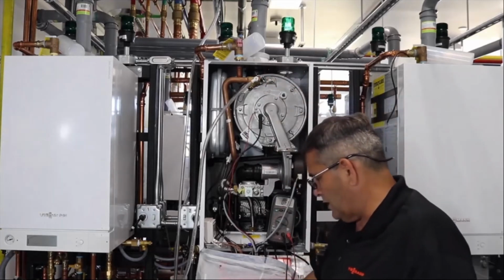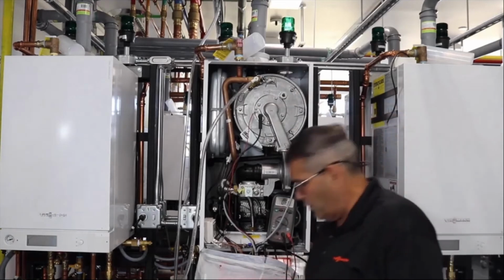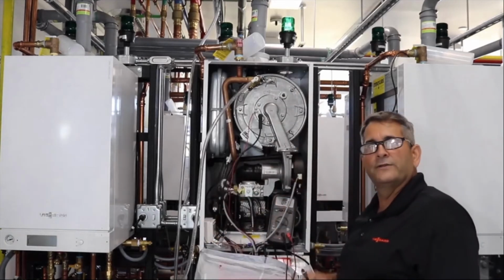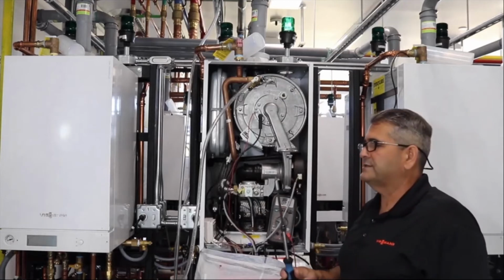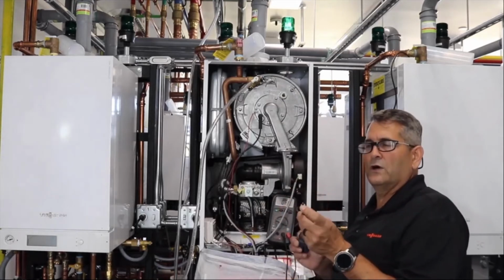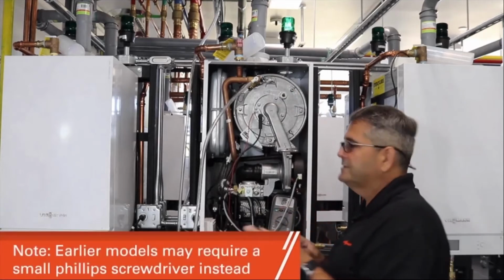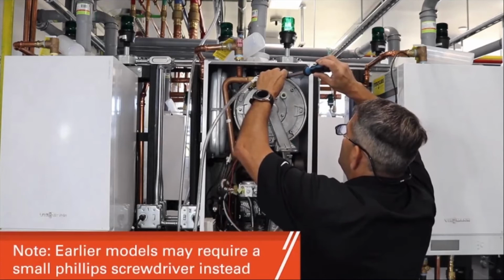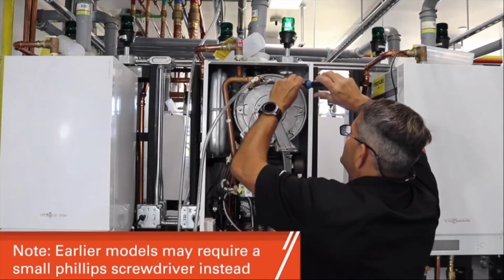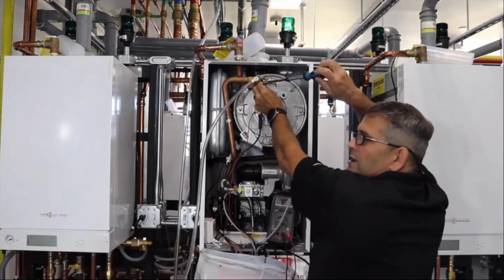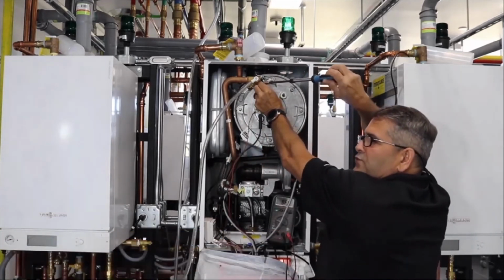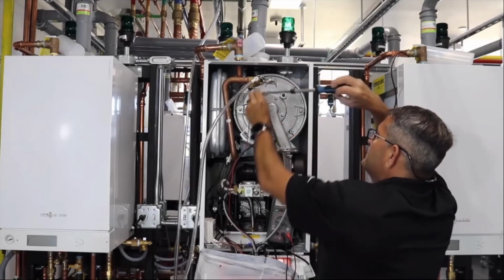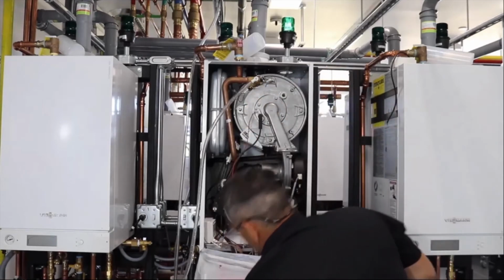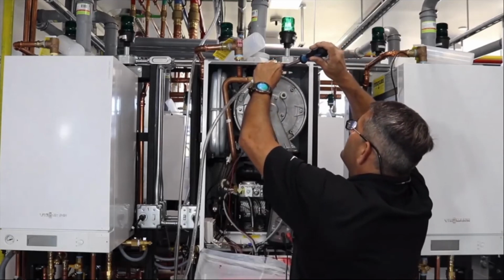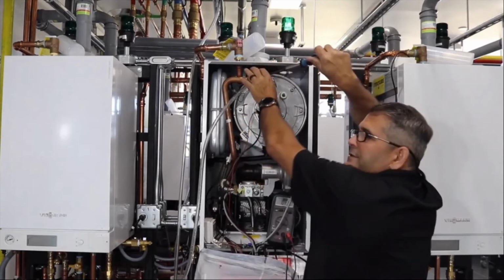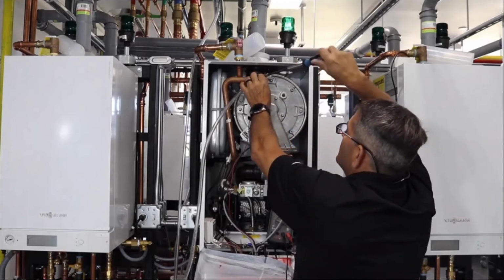and you're going to grab either your Torx screwdriver that you went out and bought, or our Torx in our toolkit that you saw in the beginning of the presentation. This happens to be a Torx 10 on this, so a T10. And there's 2 T10s on here as well. So we're going to take off the 2 T10 screws. And this is not a wet well, this is a dry well. So there's no need to drain any water out of your boiler itself. Your other ones are in wet wells, so you do have to drain the water out of the boiler. But remember, there's only a gallon of water on this boiler, so there's not a heck of a lot of water in here.